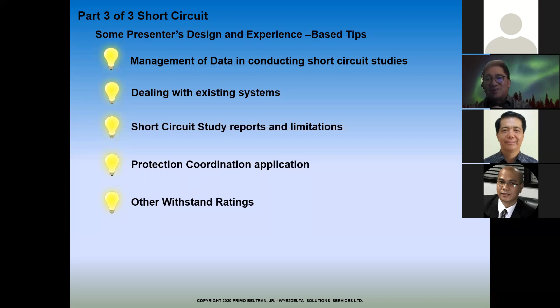Other withstand ratings - I didn't discuss the withstand rating of cables here, but that's found in manufacturer catalogs. IEEE 242 also has an equation and a list of clearing times and temperature ratings. For example, XLPE has a maximum operating temperature of 90 degrees and a maximum short circuit temperature of 250. The clearing time depends on your breaker or protective device, and there are standards in cycles for what you can use. There are equations - get them from the cable manufacturer, or their damage curve, the short circuit damage curves.